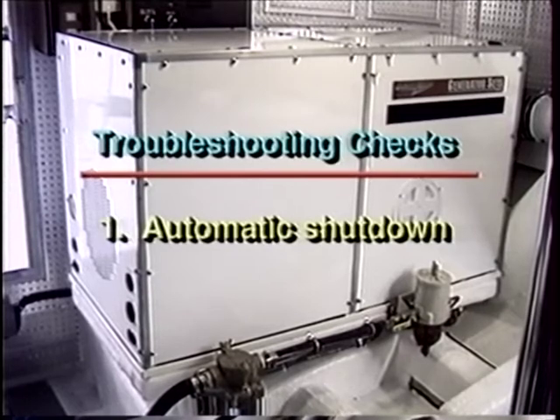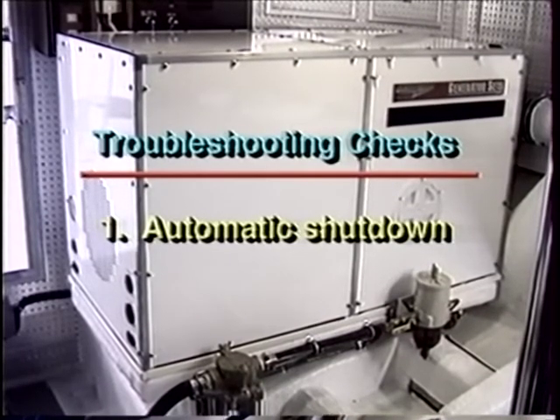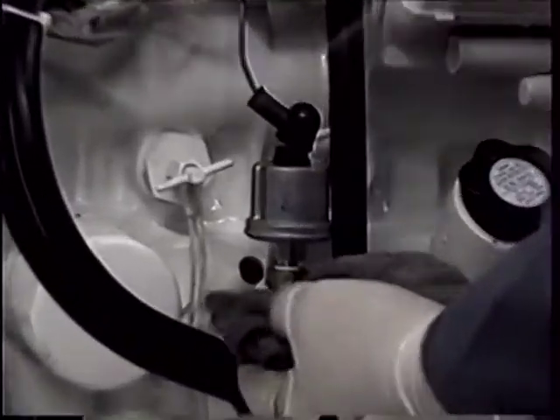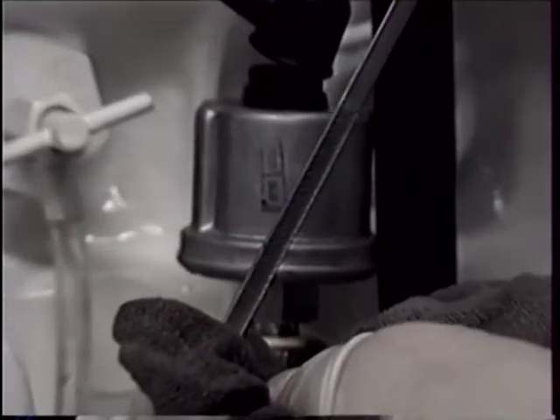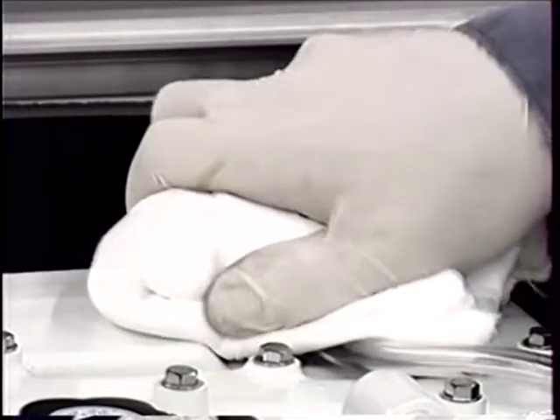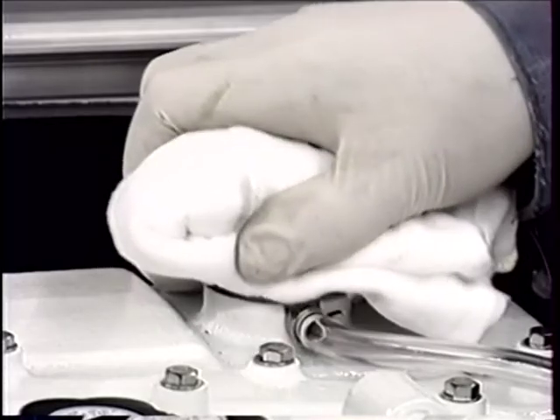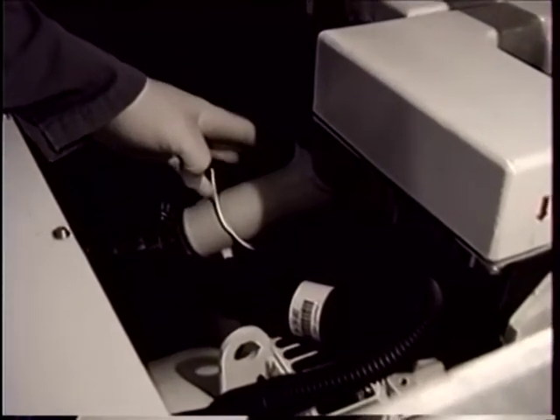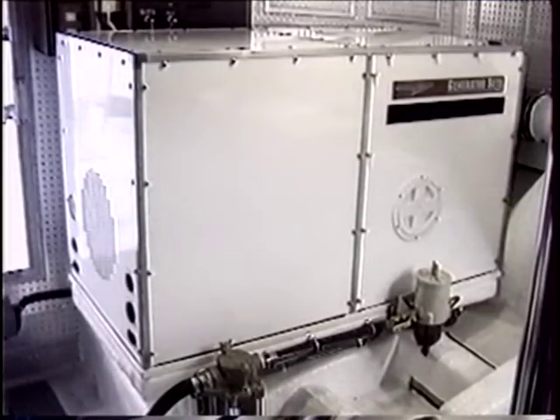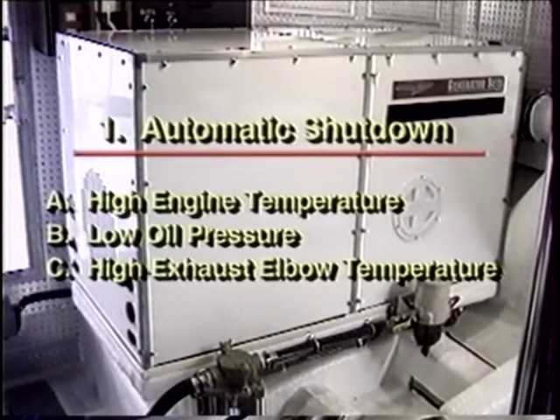What to do if the generator set shuts down on its own. While the unit is shut down, check the oil level on the dipstick, and then carefully check the coolant level in the expansion tank. After this, carefully touch the exhaust elbow or muffler to see if either is hot to the touch. The primary reasons for automatic shutdown are high engine temperature, low oil pressure, or high exhaust elbow temperature.